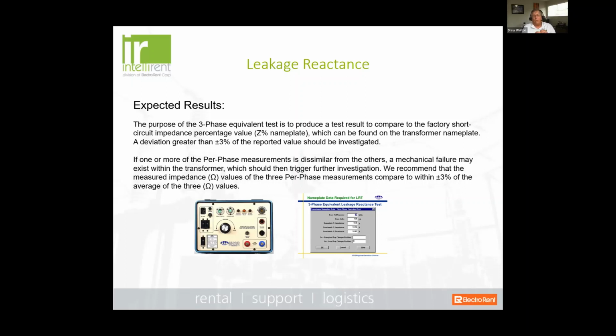So what typical tests do we see on oil-filled transformers? Well, we see a lot of different types: power factor, excitation, TTR, winding resistance. Okay, in the middle there somewhere, usually after your excitation test, should be leakage reactance. Okay, it's a simple test to perform, but why would I do a leakage reactance test? Well, a couple of reasons. Number one is that you suspect the transformer may have been subjected to through faults between the last testing cycle.